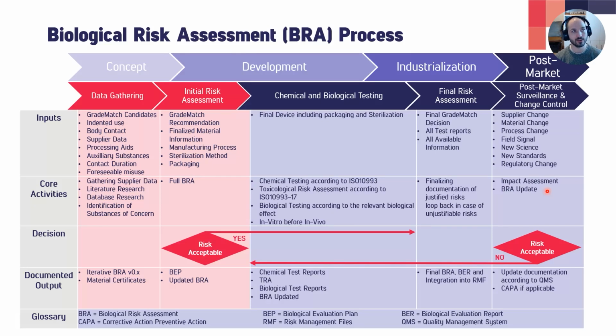For example, we have a housing of an electronic medical device that has no patient contact or only occasional patient contact, and we need to change the colorant since the master batcher has changed the colorant from one color number to the same color number from another supplier. In that case, we can probably safely say that this has no impact on the biocompatibility. But if you have an implantable device and you need to change the material or the manufacturing process, this of course has a very high impact and you will probably need to redo some of the testing. But you always make a risk assessment.